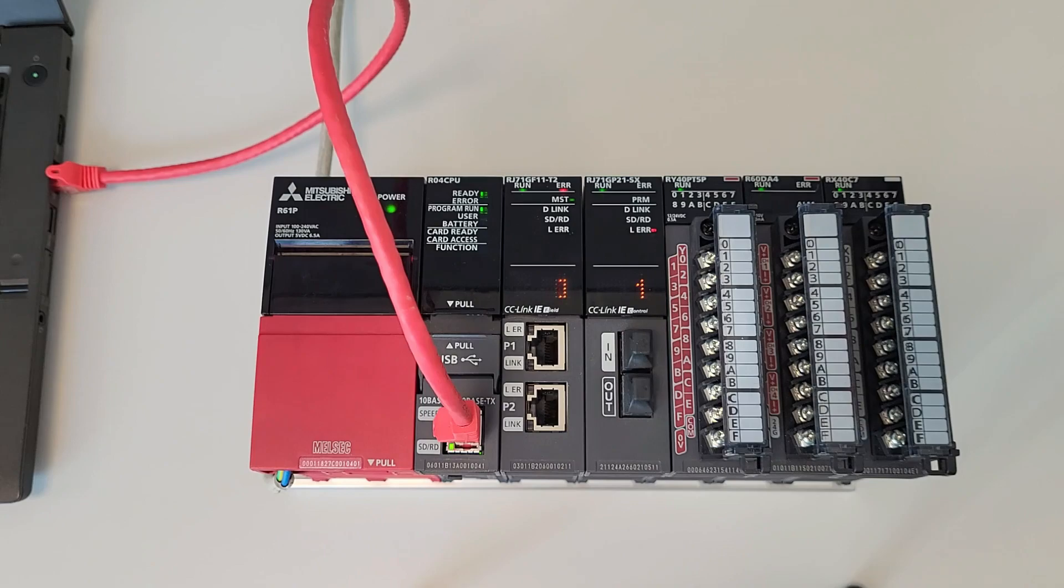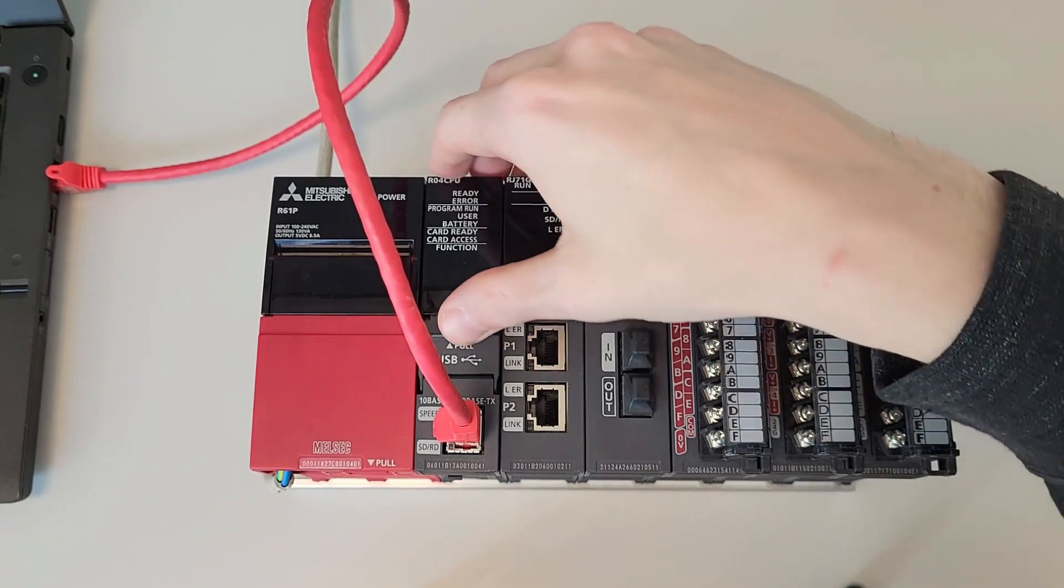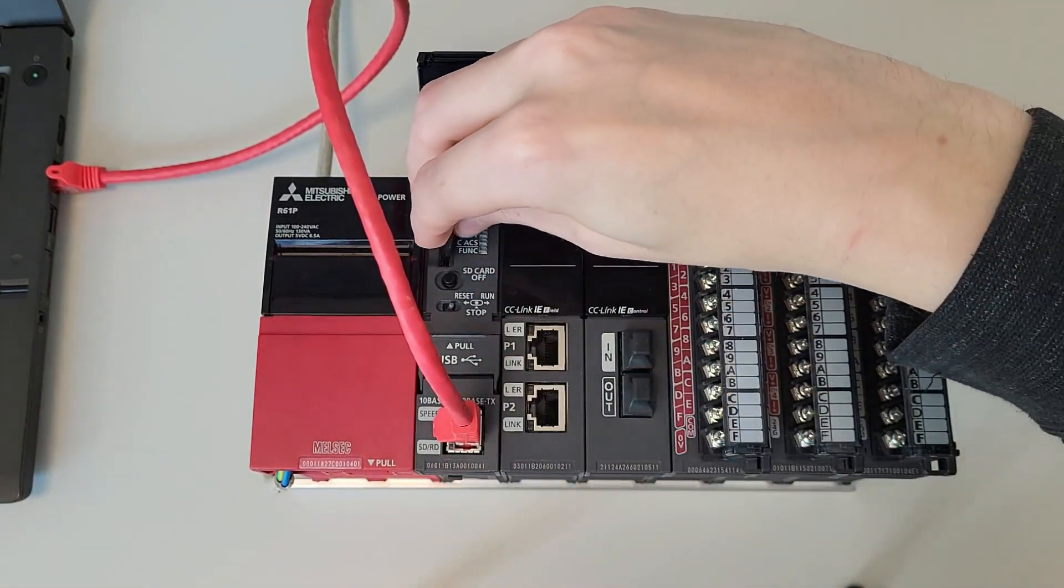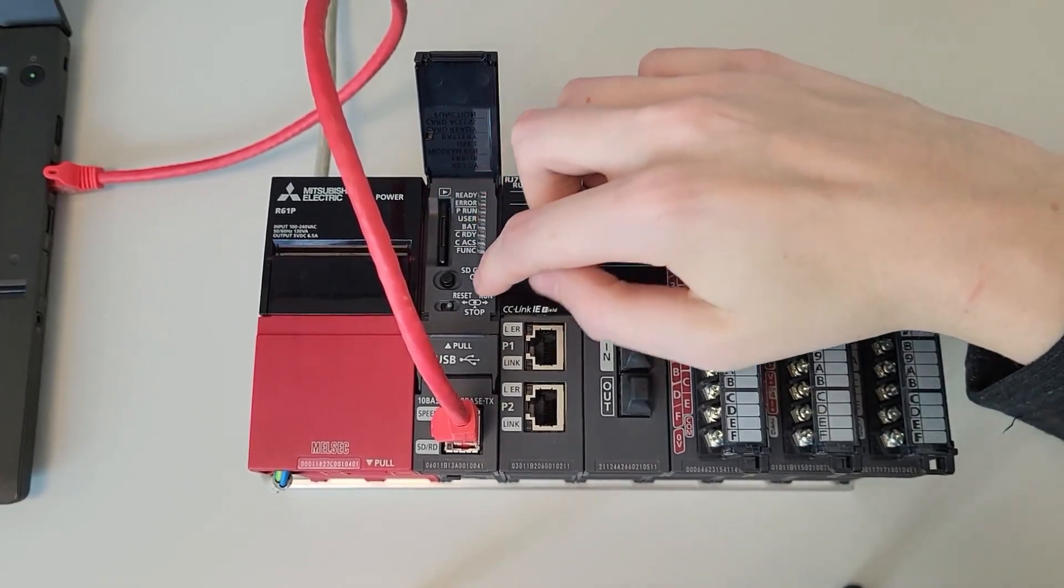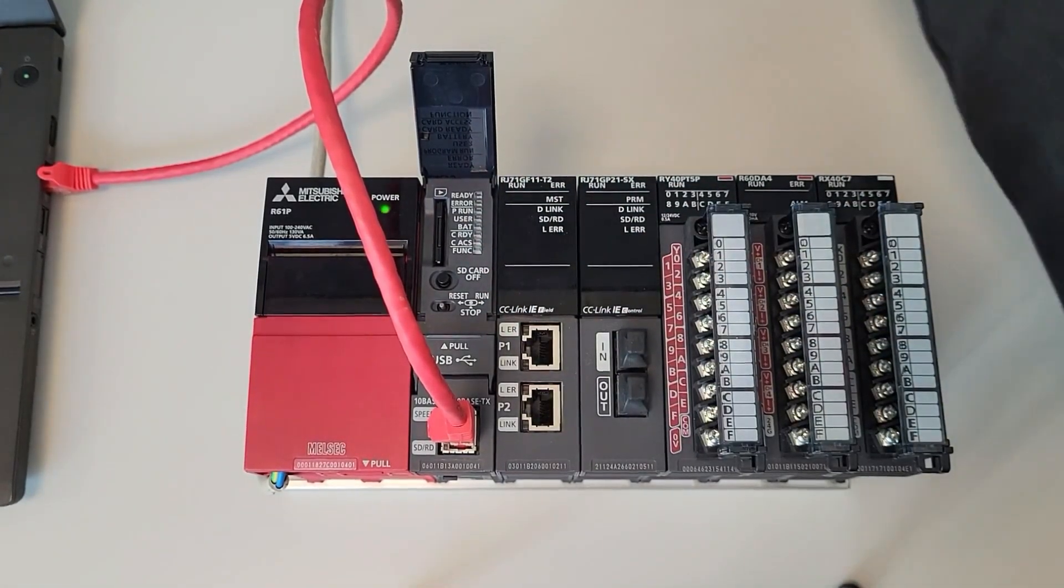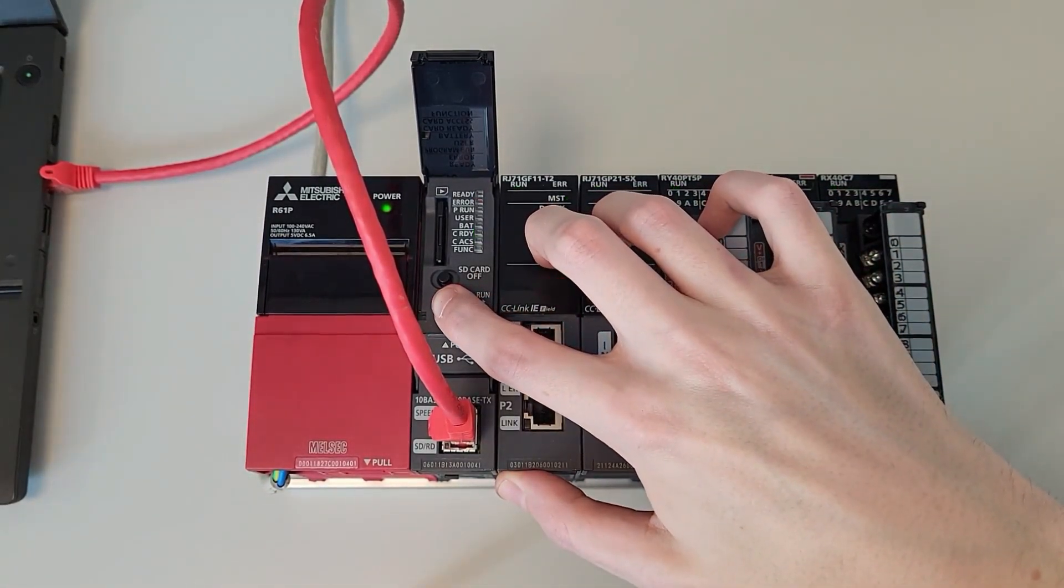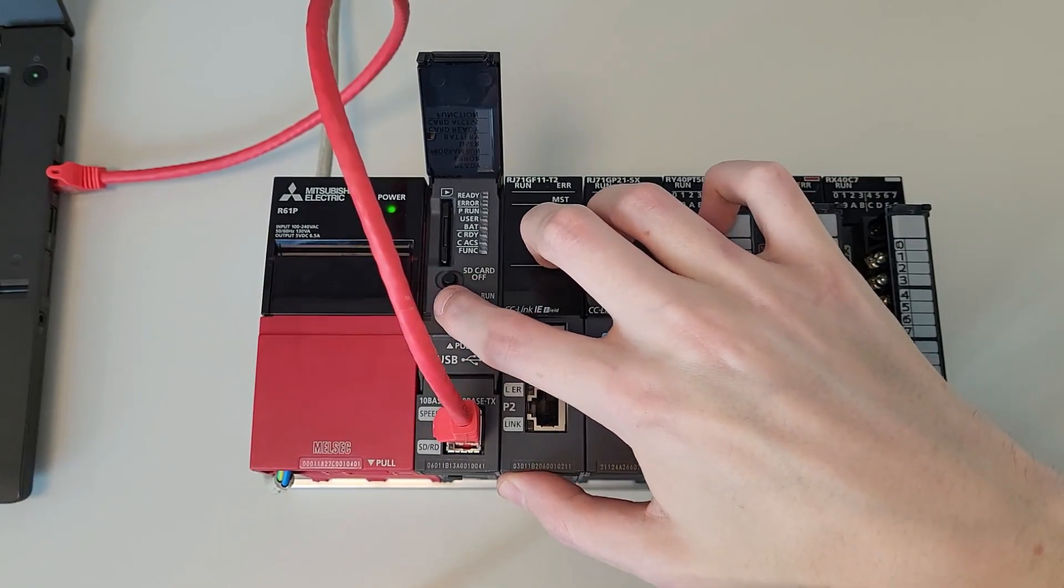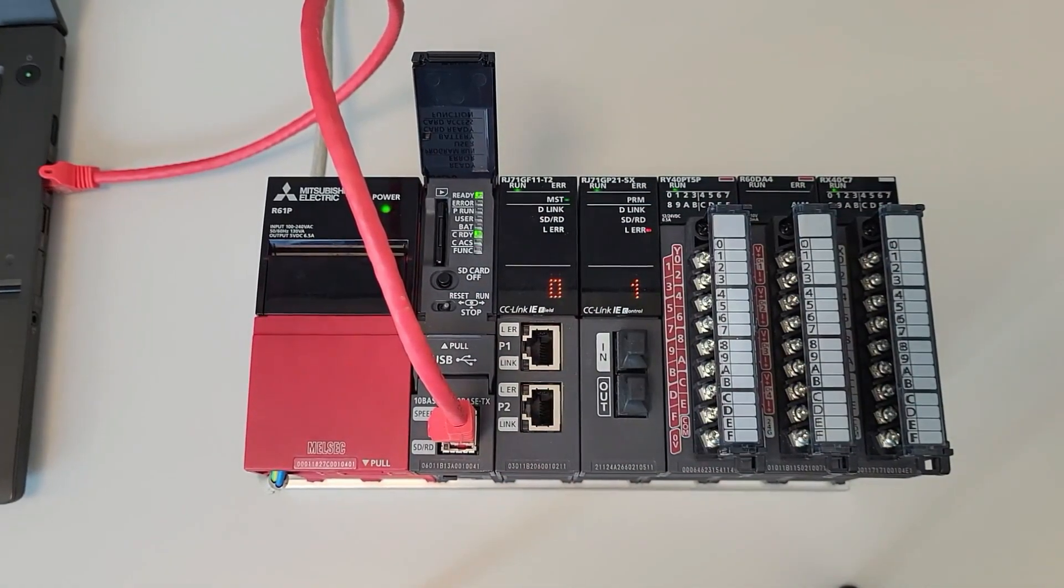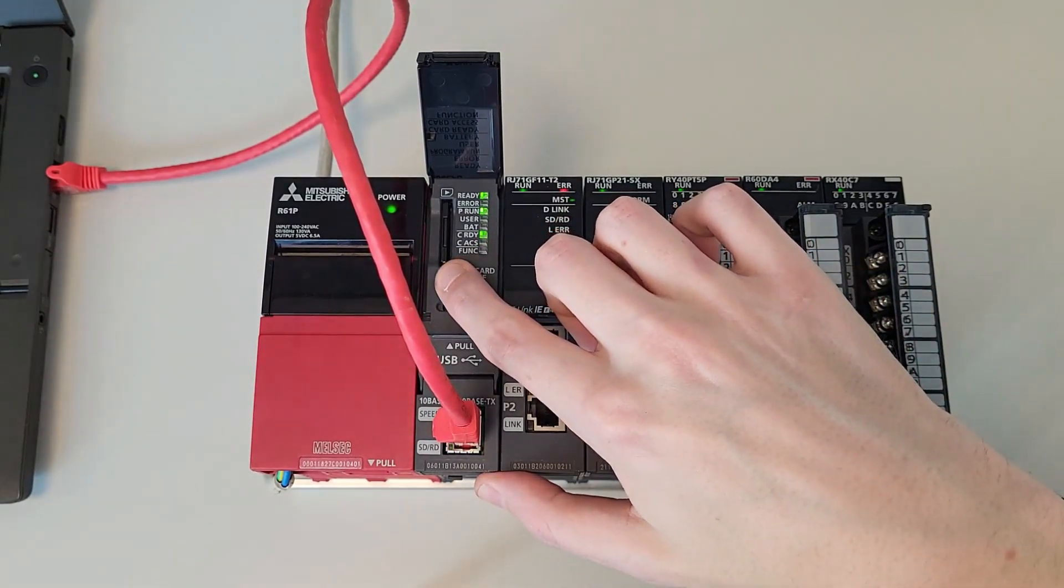For the IQ-R the procedure is the same. First of all we have to turn it off then we insert the SD card and we put the selector on stop. Then when we turn it on we take the selector on reset for three seconds and then to stop and run and it will go to run with the new files. Also here press the SD card off button to remove the SD card.